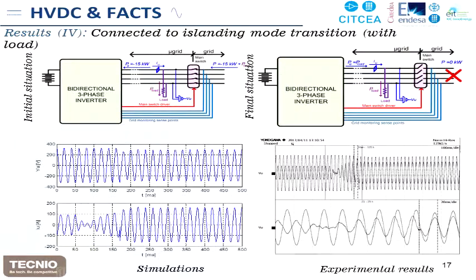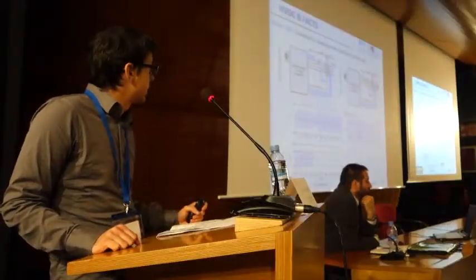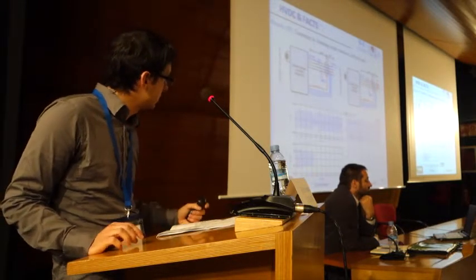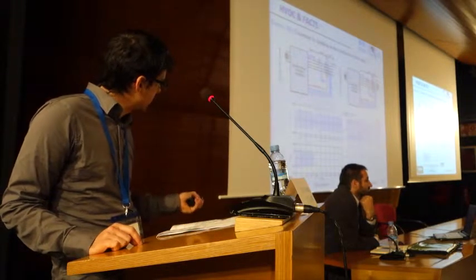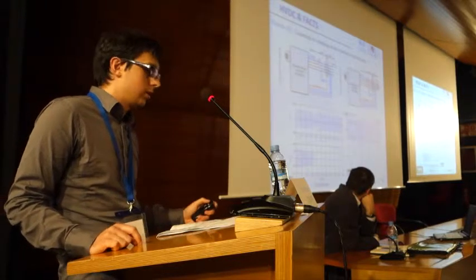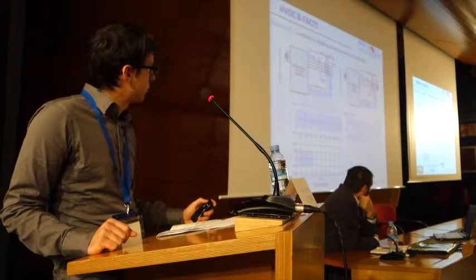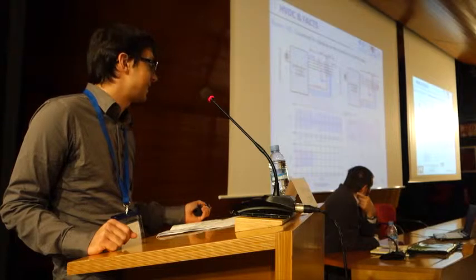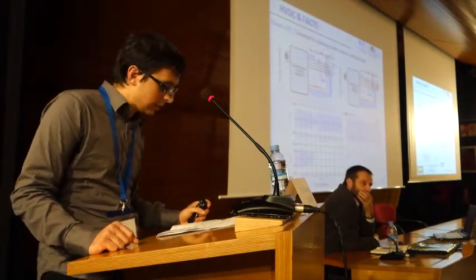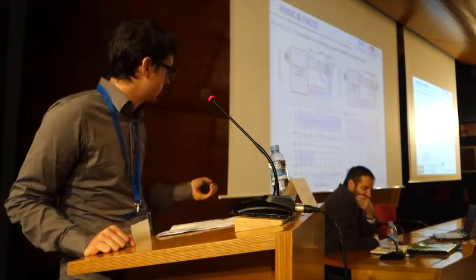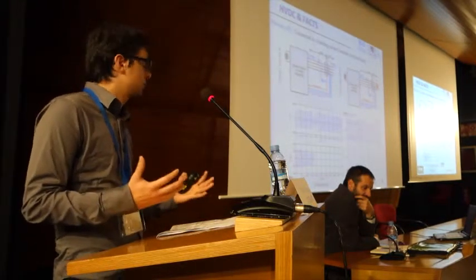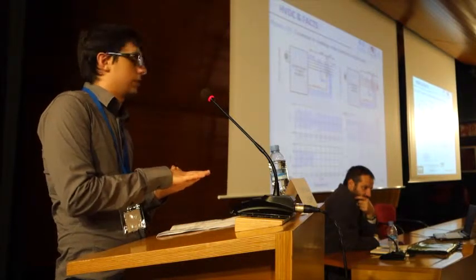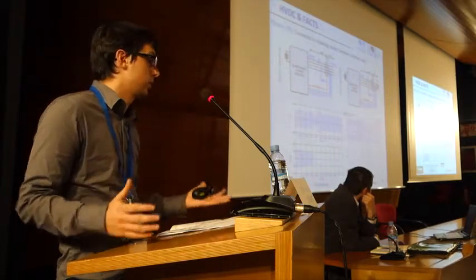So in this case, the first results are related with a reference where the system is consuming 15 kilowatts from the grid. This implies that we are injecting that power into the energy storage system. There are no loads, and suddenly we decide to open the main switch because something happens. And in these simulations, you can see here that more or less at time 50 milliseconds, the system starts to change. Here, in order to make the simulation as close as possible to the real system, we have proposed to change the operation mode at the time we send the signal to open the main switch, but the main switch doesn't really open until 170 milliseconds, so 120 milliseconds after, in order to simulate the behavior that your main switch breaker can open mechanically, but the current can still flow for some time.